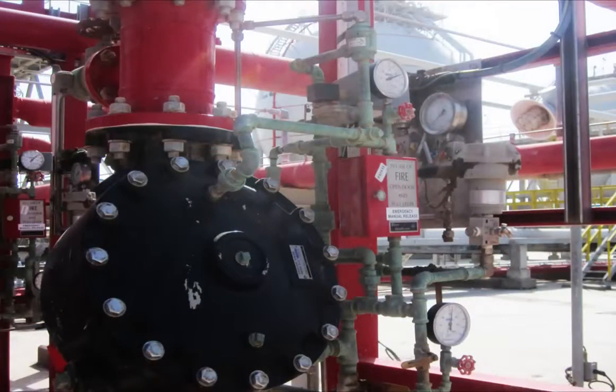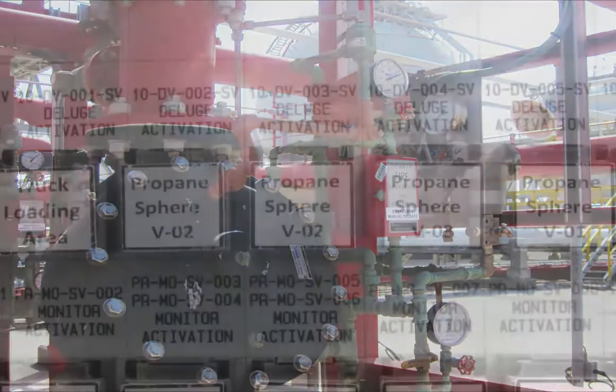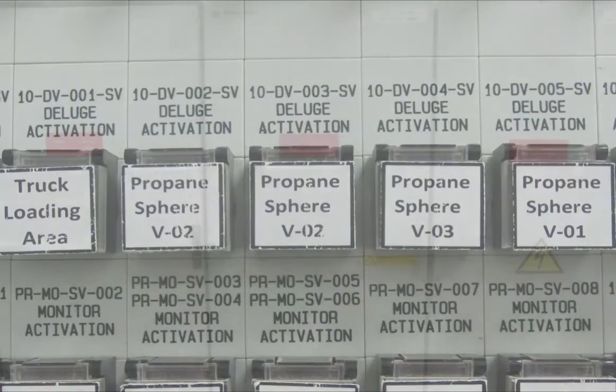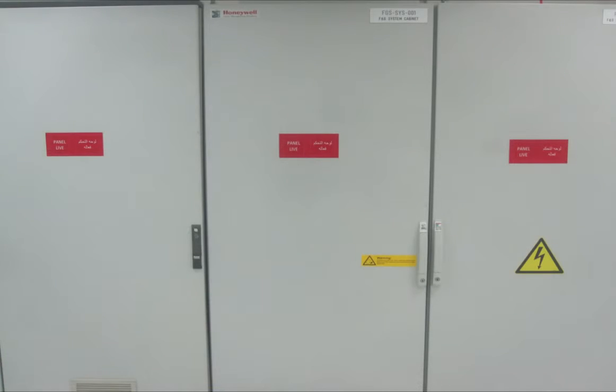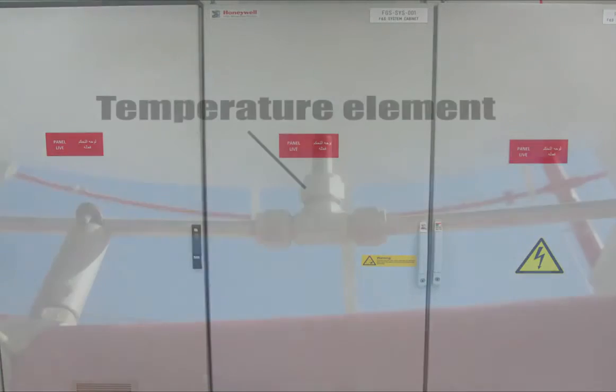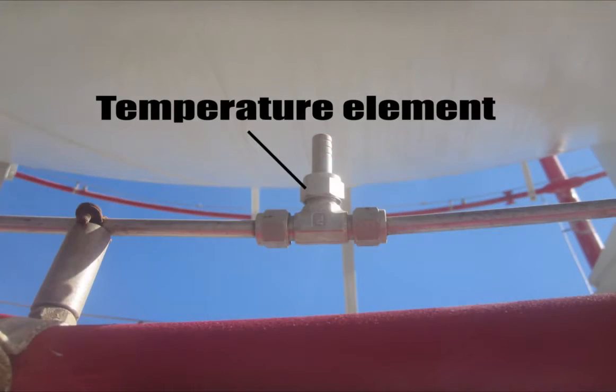The deluge valve can be operated manually using the emergency release valve that is present on the priming loop. Another method for activating the deluge system is by activating the solenoid valve, which is also present on the priming loop. This can be activated either manually by a push button in the control room or automatically from the fire and gas panel in case a temperature element senses a high temperature on the protected equipment.